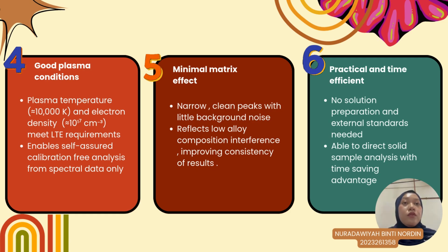The generated plasma was very hot at around 10,000 Kelvin and highly electron dense. These plasma conditions are ideal for local thermodynamic equilibrium, or LTE, which is required for accurate calibration-free analysis from emission lines. Another important strength is the low matrix effect. The emission lines in the spectrum were clear and crisp with minimal background noise. It indicates that although magnesium alloy may have a complicated composition, the measurement is stable and accurate.